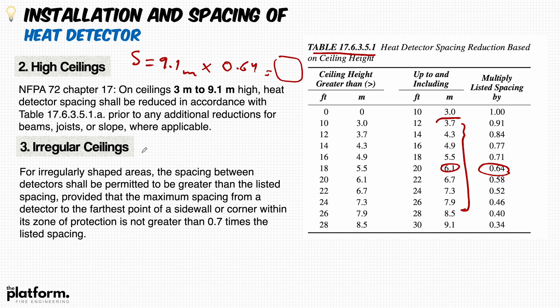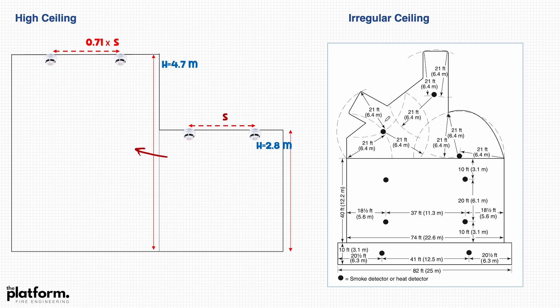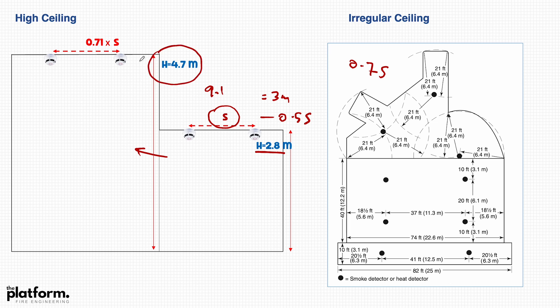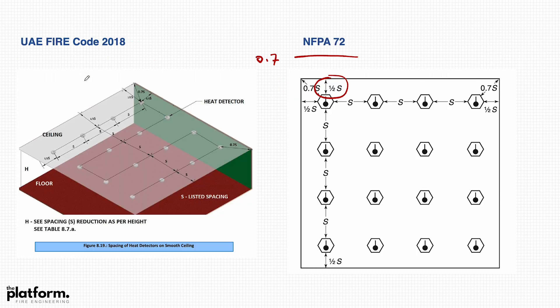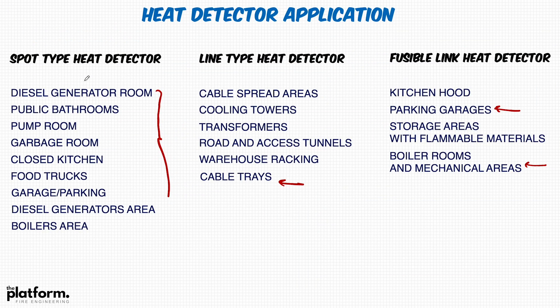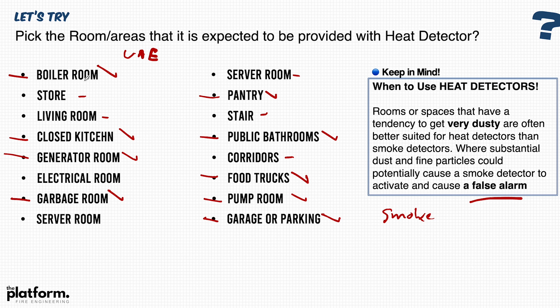For irregular ceilings, any point on the ceiling shall not exceed 0.7 of the listed spacing. In a room with standard height up to 3 meters, follow the standard listed spacing of 9.1 meters and apply 0.5 times the spacing from the wall. If the height is more than the standard 3 meters — for example up to 4.7 meters — refer back to the table and multiply the listed spacing by the appropriate reduction factor. We have covered heat detector types, spacing between detectors, and applications in auxiliary and special rooms. Stay tuned for the next lectures by the Platform of Fire Engineering. Thank you so much.